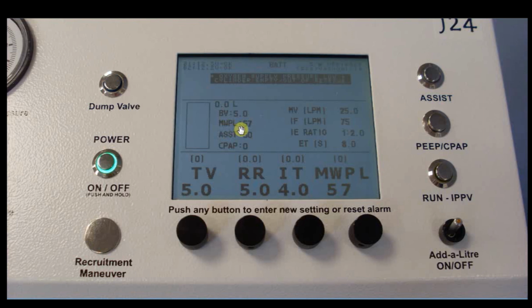Under here we have MWPL, which is mirrored down here by the MWPL button, and at the moment it's set to 57. That's centimetres of water, and MWPL stands for maximum working pressure limit. What this means is that if the pressure in the circuit ever reaches this value of 57, which is unusually high, would normally be expected to set around 30 to 35, then the dump valve will open and any excess gas will be allowed to escape, and if we're ventilating, the inspiratory phase will stop. So it's a safety feature, and the pressure won't be allowed to rise above the value that's set by the MWPL.